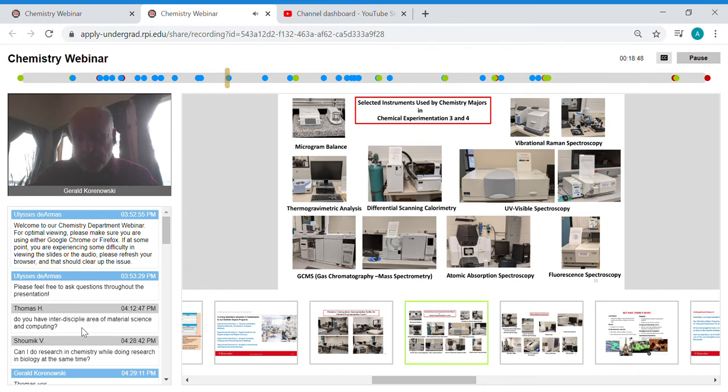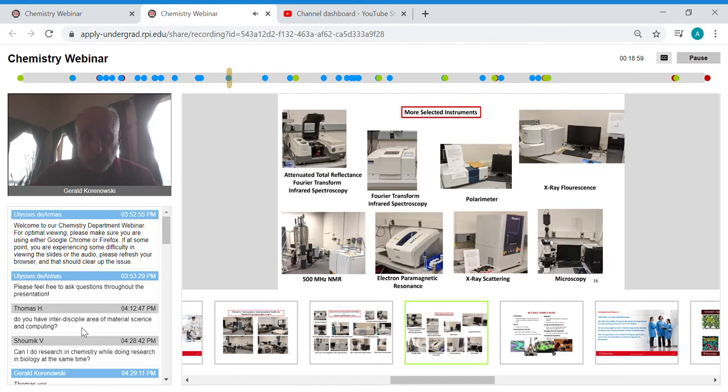Right next to it is a fluorimeter. It's kind of the opposite of a UV visible. It looks at the emission of light once we excite it. Okay, next slide. We have two infrared spectrometers in the upper left-hand corner. They do kind of the same thing as Raman, but with infrared absorption. They're all Fourier transform machines now. One is a straightforward absorption, the one to the inside. The one with the hood up on it is an attenuated total reflection Fourier transform. Right below that hood is a little silver anvil with a tiny diamond window set in it that you put your sample on, and the infrared absorption is done in reflection off of that diamond window.